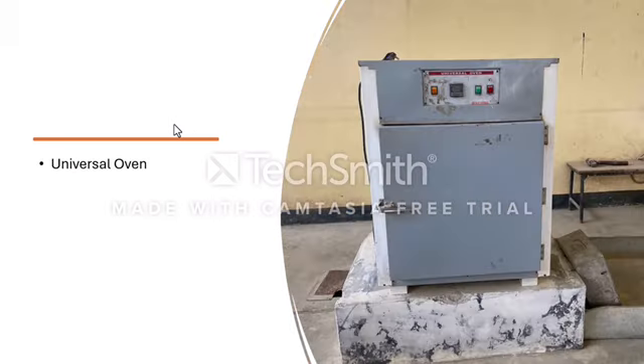And the next one is the universal oven, which costs around 41,500 to 2,49,000 based on size, temperature range, and features. Its function is used for drying, curing, and baking samples in a controlled environment, and its principle is to provide uniform heat distribution through natural or forced convection, maintaining a consistent temperature to achieve desired sample conditions.